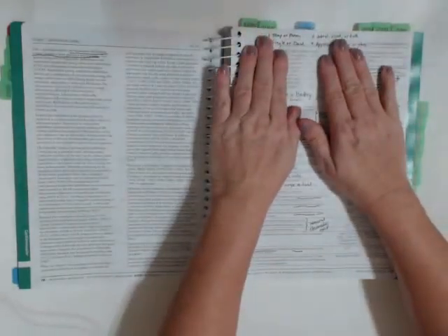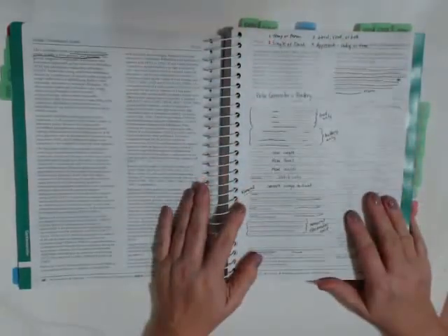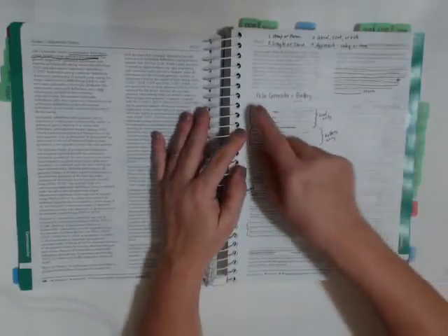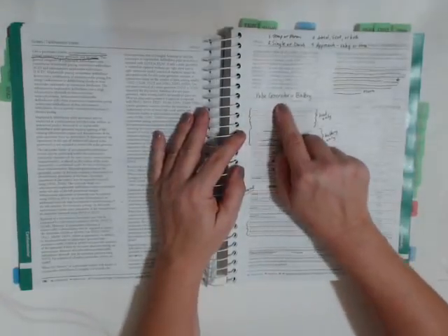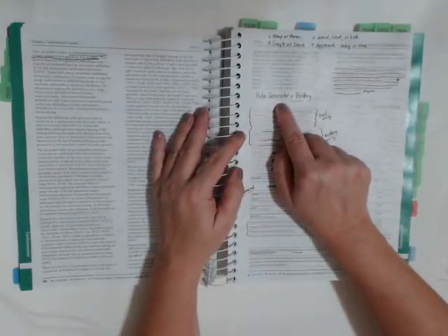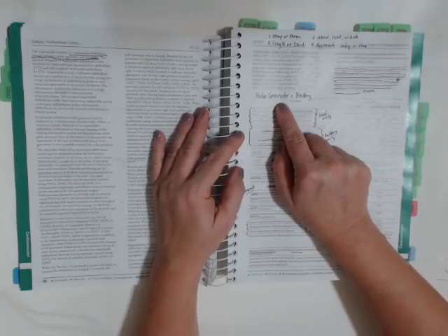Now, obviously, the first question that isn't even listed here is, is it a pacemaker or defibrillator? Anytime you see lingo, pulse generator, that's the battery. You might see battery and your code description says pulse generator, or vice versa. They're the same thing.